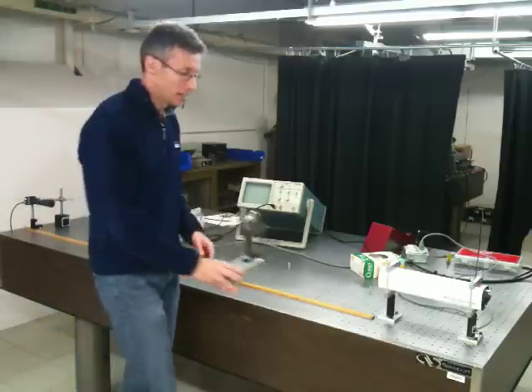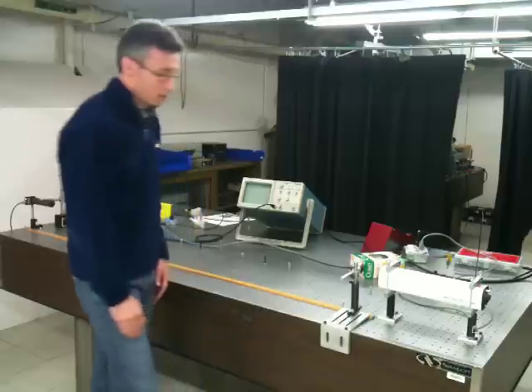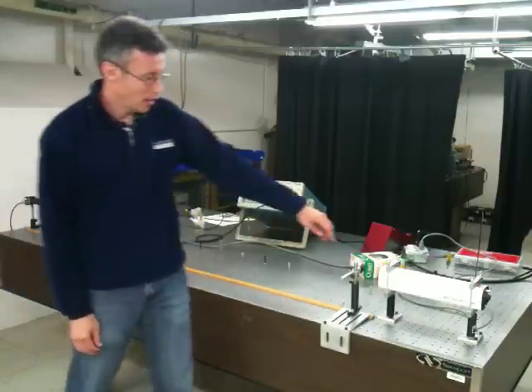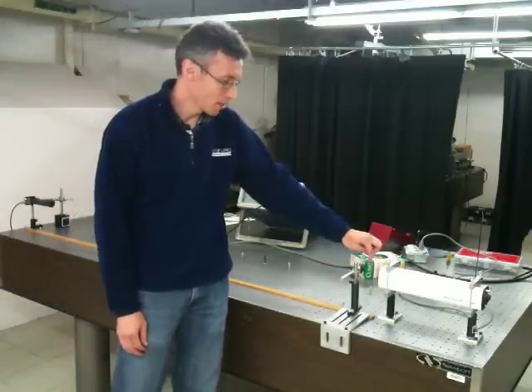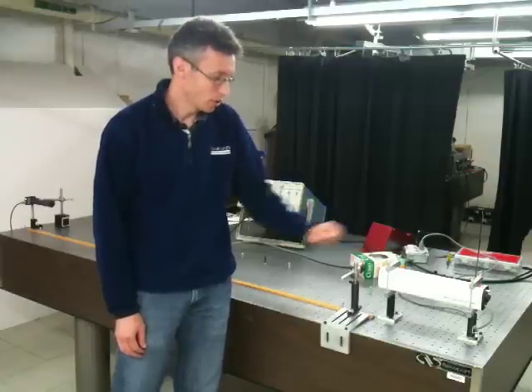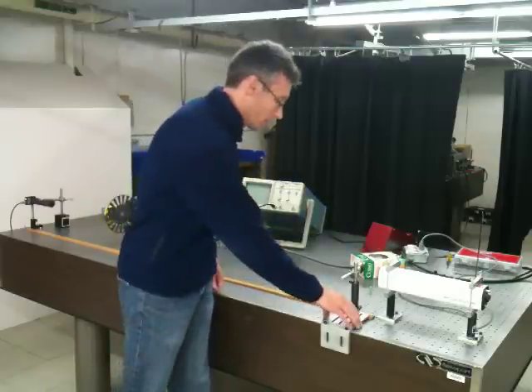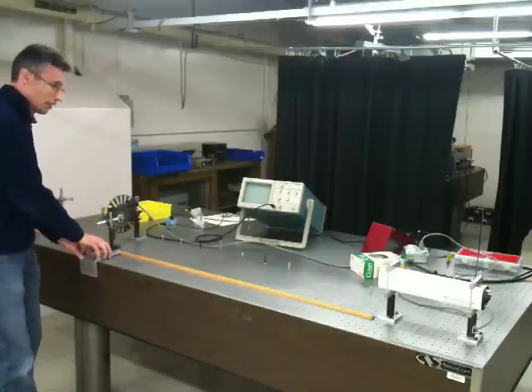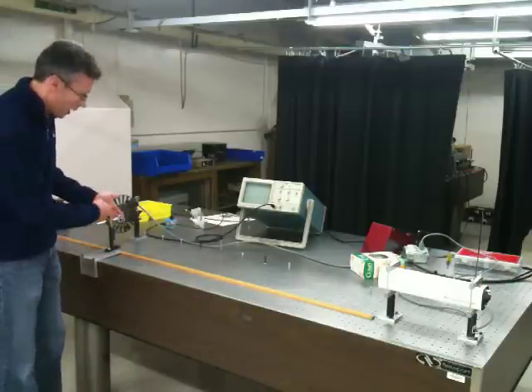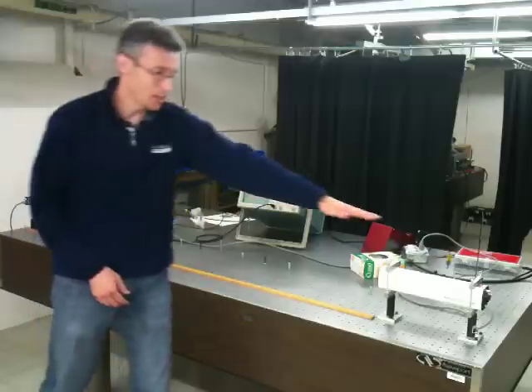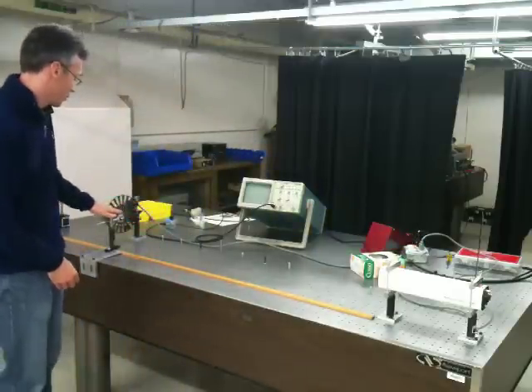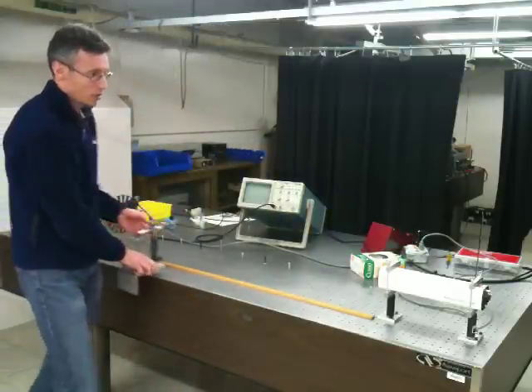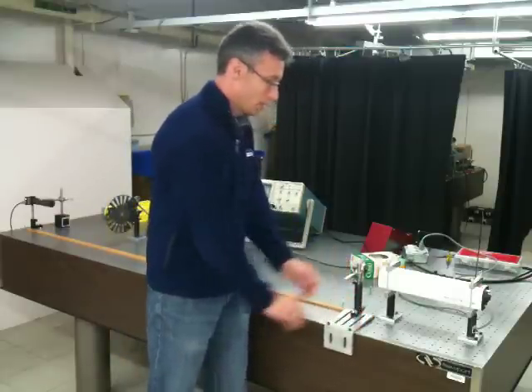So I've put together a little jig here that I can position on the table. I've got an iris on the end and I'll adjust the location of this iris so that the beam passes through when placed just in front of the laser. And now I can move this down to the other end of the table and observe that the beam passes through. If it doesn't, I can adjust the tip and tilt to this laser so that the beam does pass through. And then it's worth checking that the initial point hasn't changed.